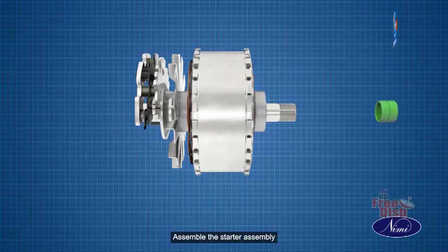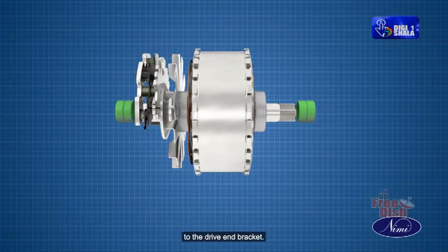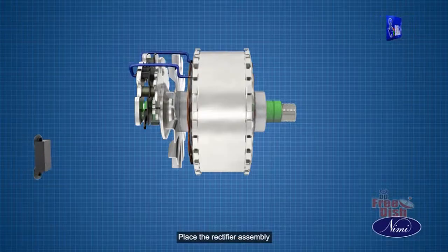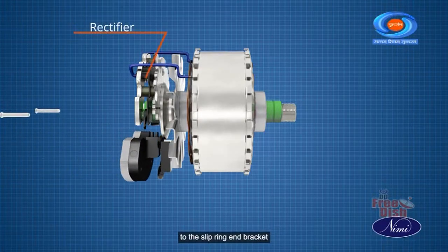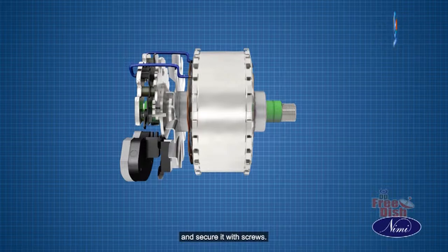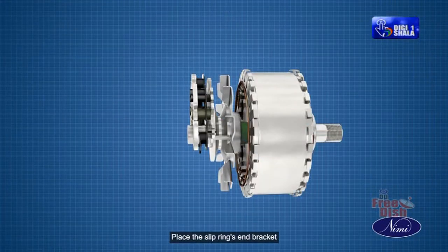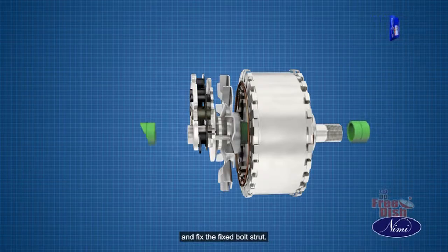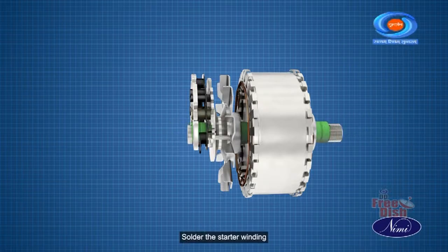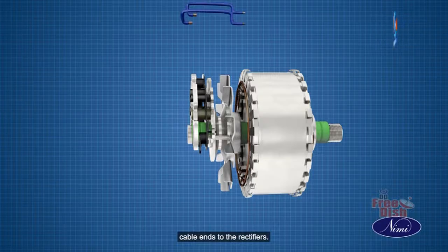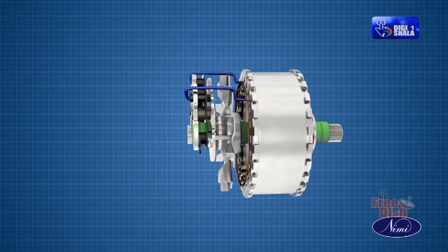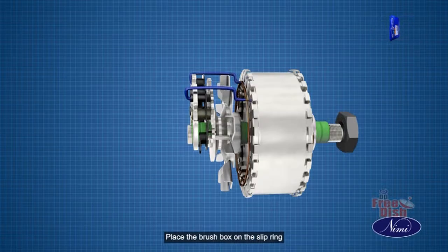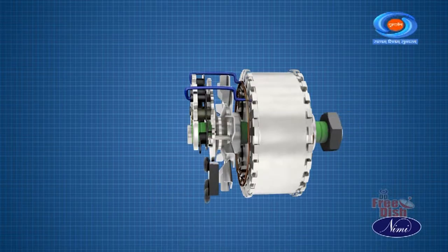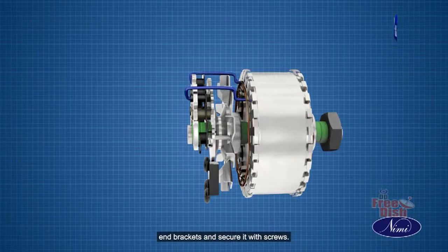Assemble the stator assembly to the drive end bracket. Place the rectifier assembly to the slip ring end bracket and secure it with screws. Place the slip ring's end bracket and fix the fixed bolt stud. Solder the stator winding cable ends to the rectifiers. Place the brush box on the slip ring end brackets and secure it with screws. Place the sealing pad and position both brushes.